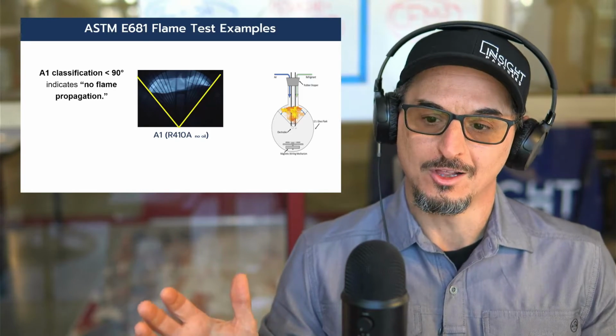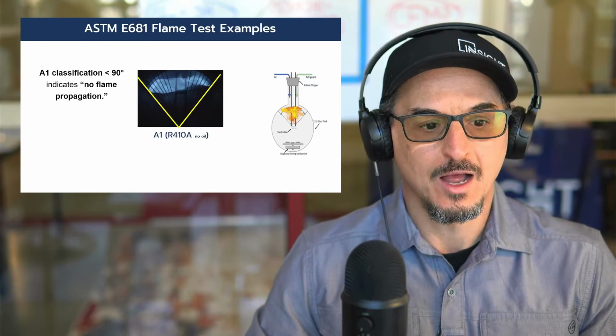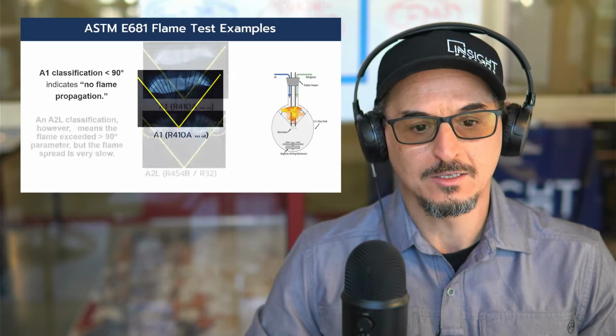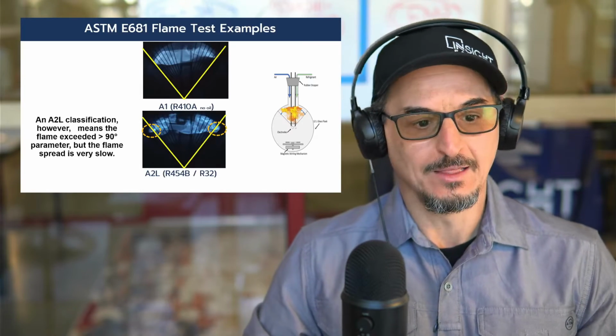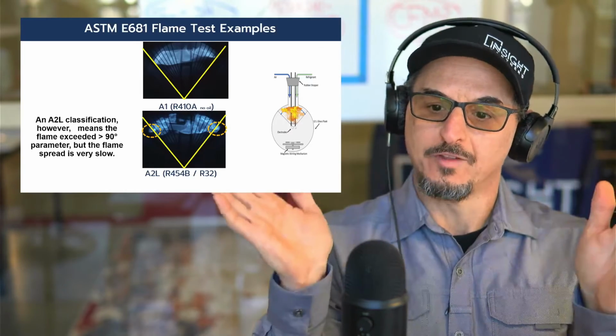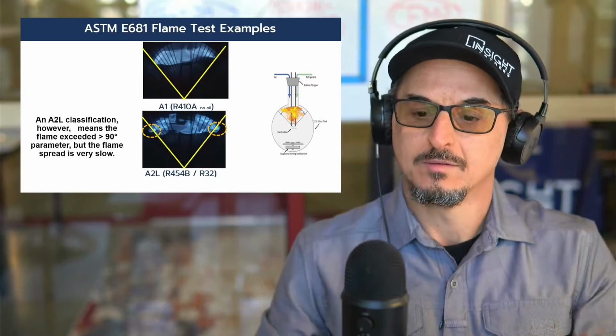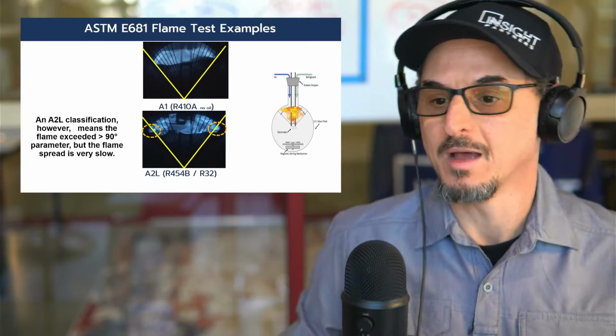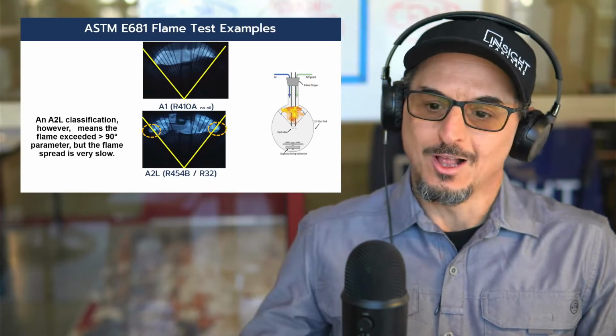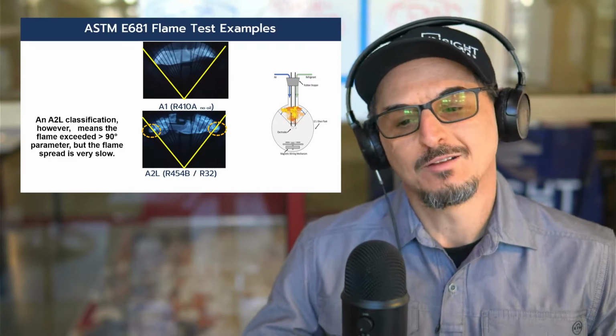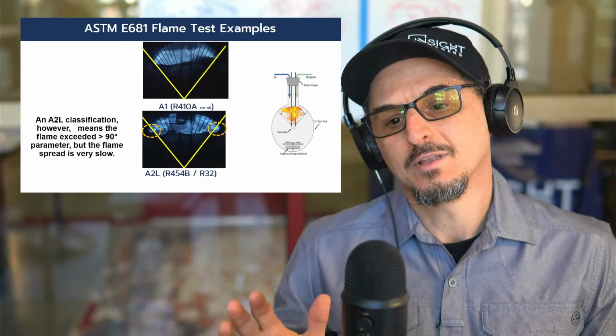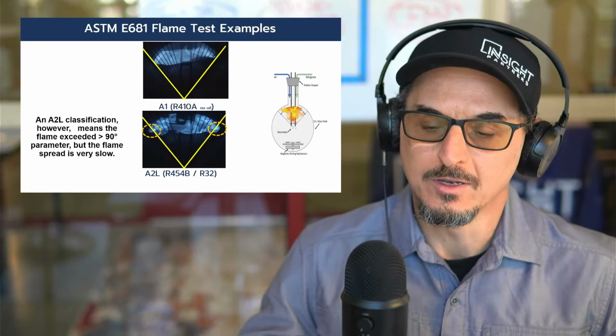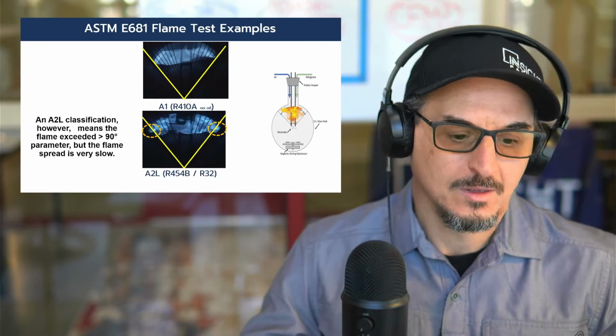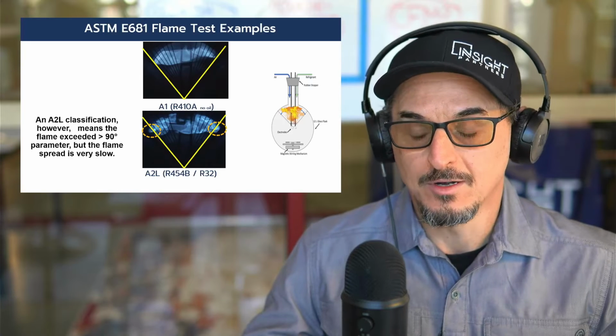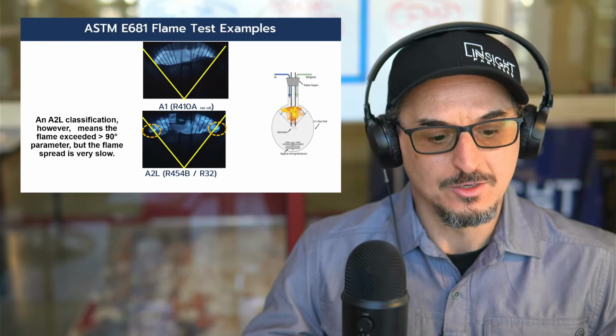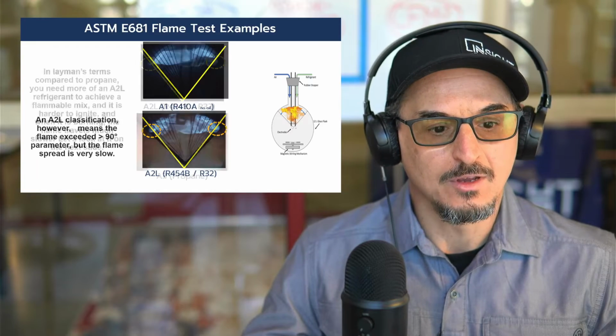So what do you think it's going to look like if we put an A2L refrigerant in here? How much is this flame going to spread over those lines? Well, there you go - that little extra bit of flame propagation is one of the things that pushes it into the A2L classification. So it's not really flammable, it's not non-flammable. That A2L classification is relatively new, maybe 10 years old. By the way, these refrigerants, R32 and 454B, aren't new - they've been around a while. They're just newer to our commercial and residential HVAC.